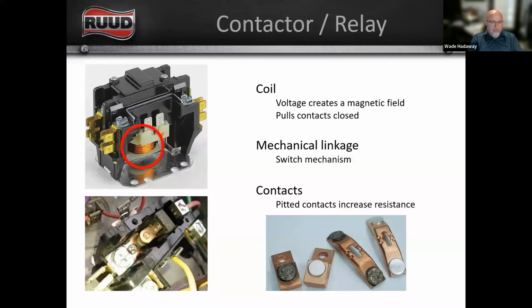If you notice, the contacts on this contactor look very similar to the contacts at the bottom right of the screen. We've got two sets. We've got a nice new clean set of contacts, and then we've got some contacts that are pitted or damaged. If you have contacts that are not closing completely, you could have some debris in there keeping them from closing all the way, or you could have insufficient voltage, not a strong enough magnetic field created by your coil to really pull those contacts all the way. Sometimes you'll hear what's called chattering contacts, meaning that they make a chattering noise because they're not closing and sticking closed like they should.